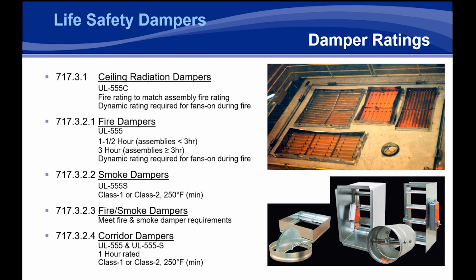Now, there have been some clarifications of some of these changes as things have gone through. One thing, the 2015 version of the code did put in language to require the need for a dynamic rating on a ceiling radiation damper if there's a dynamic system during the event of a fire.